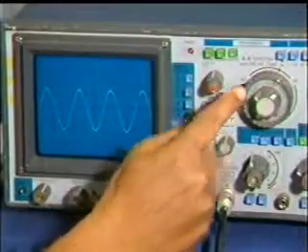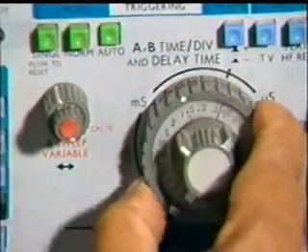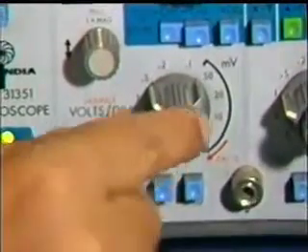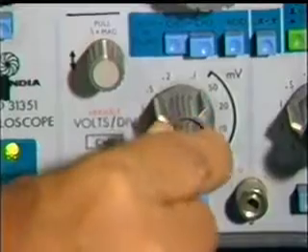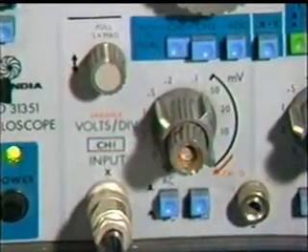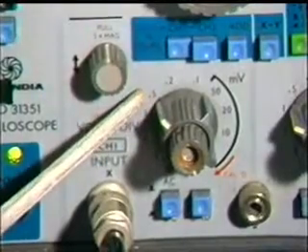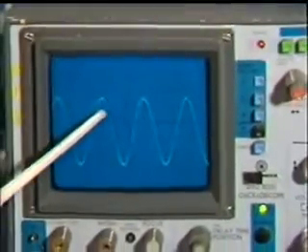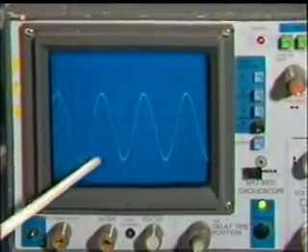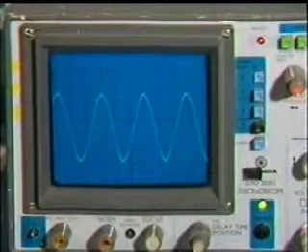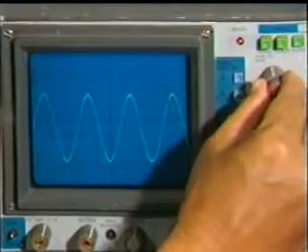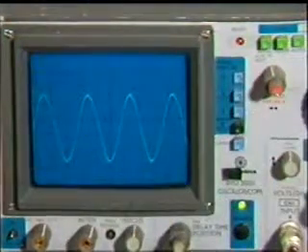Several cycles on the screen can be obtained by varying the time division knob. Before commencing voltage measurement, set the variable attenuator knob to the calibration position. Align the peak position of one cycle with the vertical center line using the horizontal positioning control knob, and align the signal peak with the horizontal line using the vertical positioning control knob.